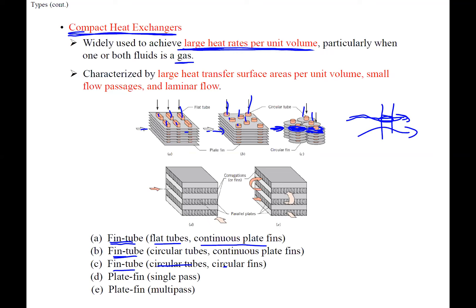Fins increase the surface area that the gas contacts, resulting in more heat transfer compared to just bare tubes. Some designs are plate-fin with fins on both sides — useful for gas-to-gas applications. Single-pass and multi-pass configurations exist. Multi-pass designs have the flow turn on alternating sides. These fins are similar to what you'd see in a car heat exchanger, creating a ceiling and maximizing surface area.